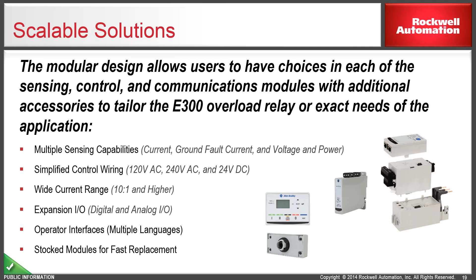The diagnostic station helps you to diagnose and configure. It has some LEDs, some navigation keys and the motor control parameters. So in case of any failure in communication with the controller, you can configure it locally. Locally you can configure the E300 with this diagnostic station and set the parameters. So this is basically showing you what motor diagnostics are available. This is a web server, so you just need to put in the IP address and you can configure the parameters: the voltage, current, energy. It will help you to have the trip and warning histories, motor winding temperature, trip snapshot, time to trip, time to reset, operational hours, and number of starts. So constantly all the parameters you can get on the web.